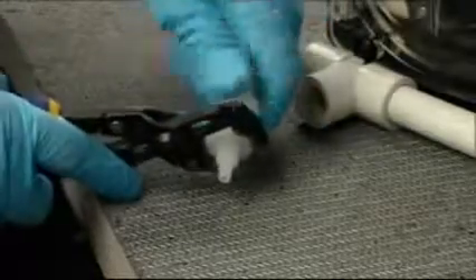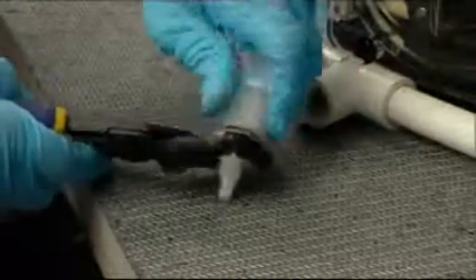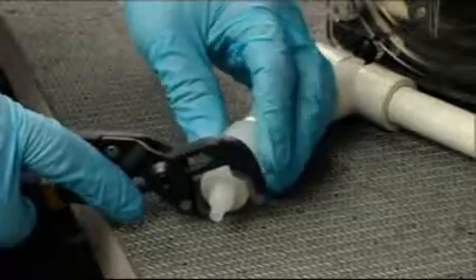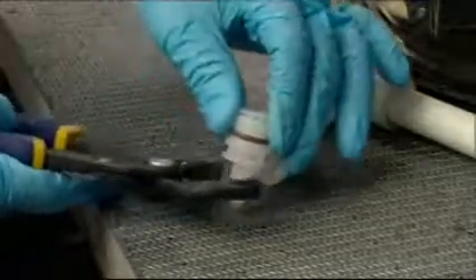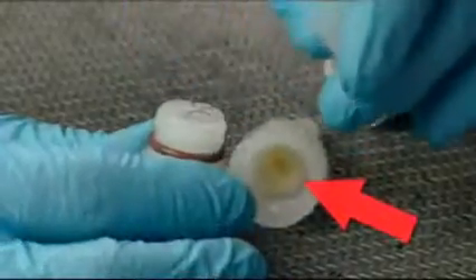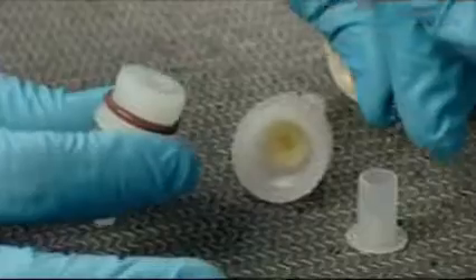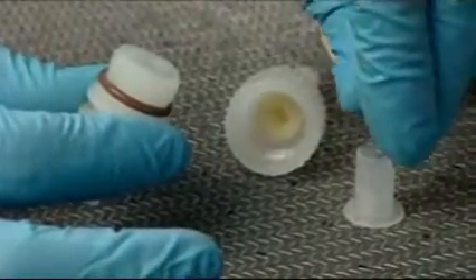If required, remove the fitting from the piping system. Disassemble the fitting and inspect the components. Clean if necessary. Replace any worn O-rings. There are 2 valves inside the assembly. The duckbill valve is made from santoprene material. It is designed to minimize calcium buildup when pumping chlorine.